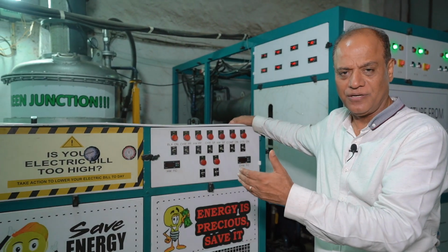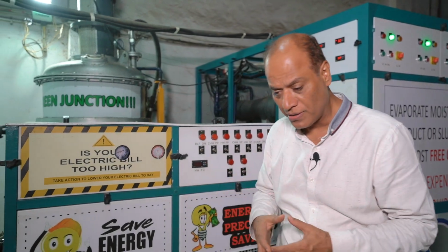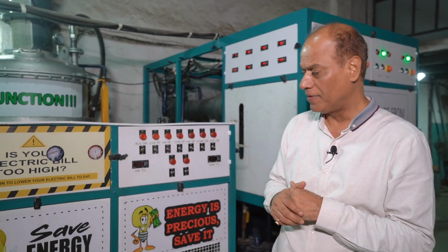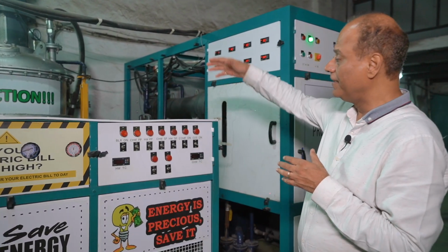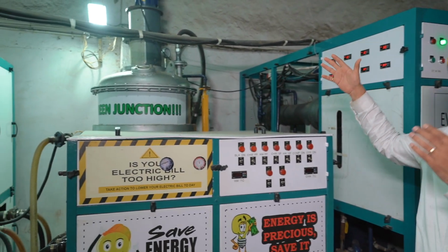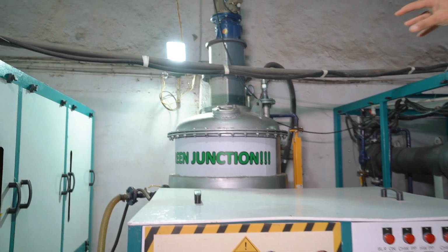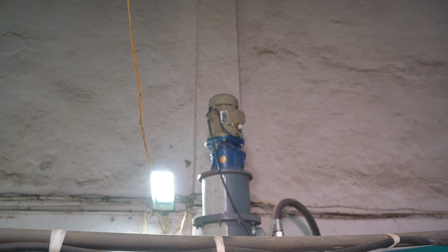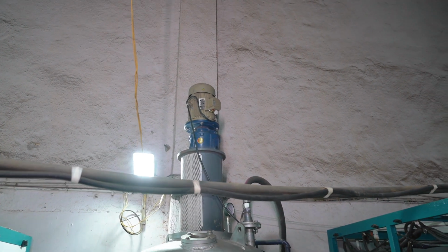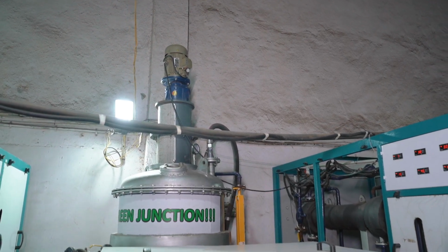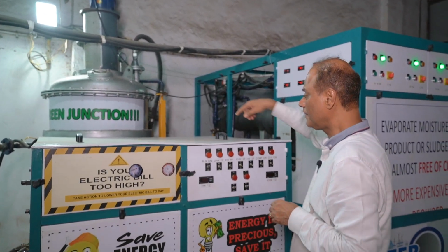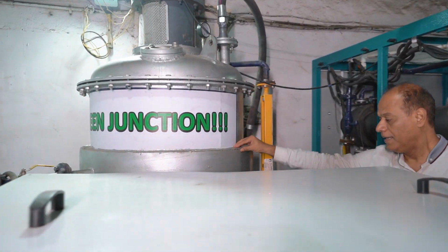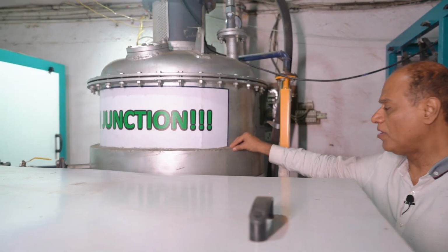And the waste condenser heat is used to generate hot water, which can be up to about 55 degrees centigrade or even 60 degrees centigrade. What you see here is a sludge tank, or an evaporator, you can call it an evaporator. What you see on top is the sludge motor, which is rotating the sludge so that there is effective heat transfer between the hot water jacket and the inner liquid. What you see in this particular section is nothing but a hot water jacket.